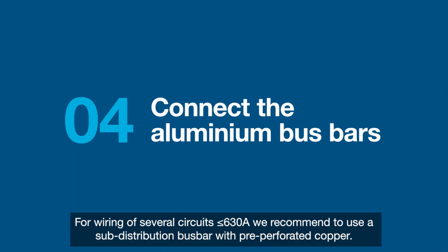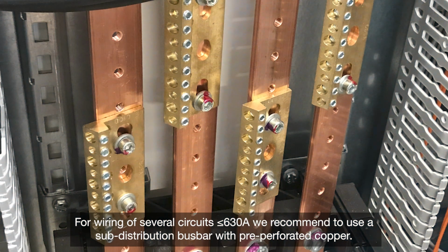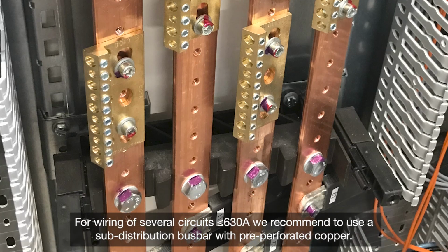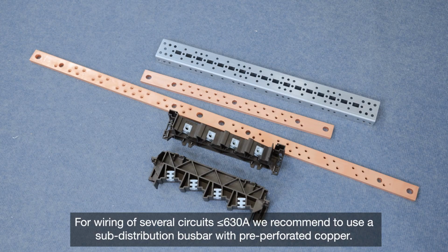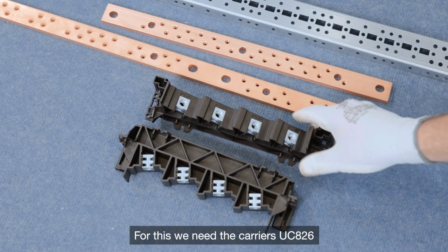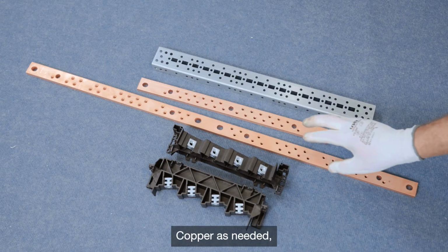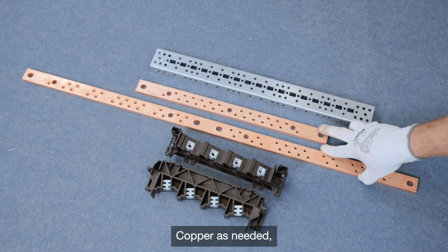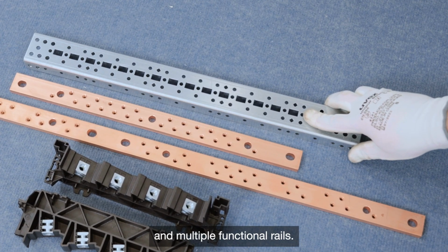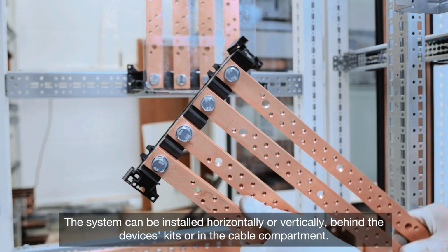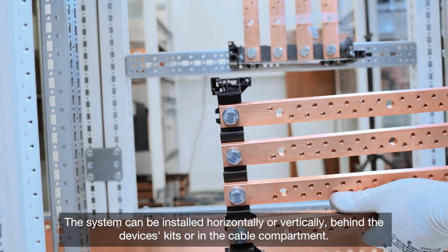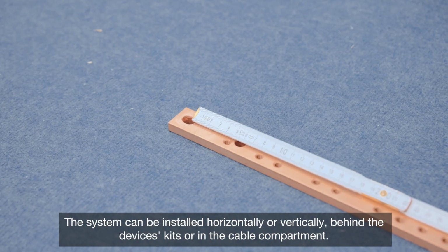For wiring of several circuits less than or equal to 630A, we recommend using a sub-distribution busbar with pre-perforated copper. For this we need the carriers UC826. Copper as needed. And multiple functional rails. The system can be installed horizontally or vertically, behind the device's kits or in the cable compartment.